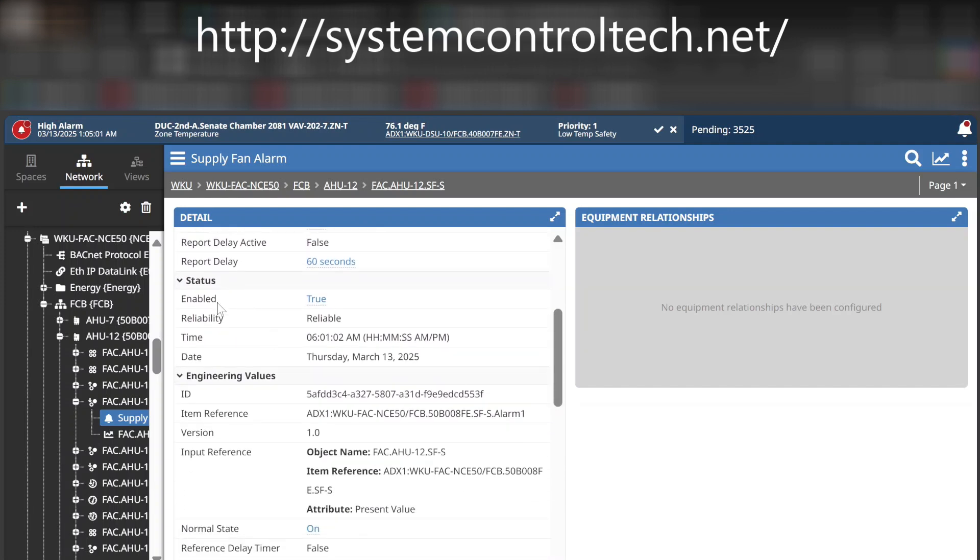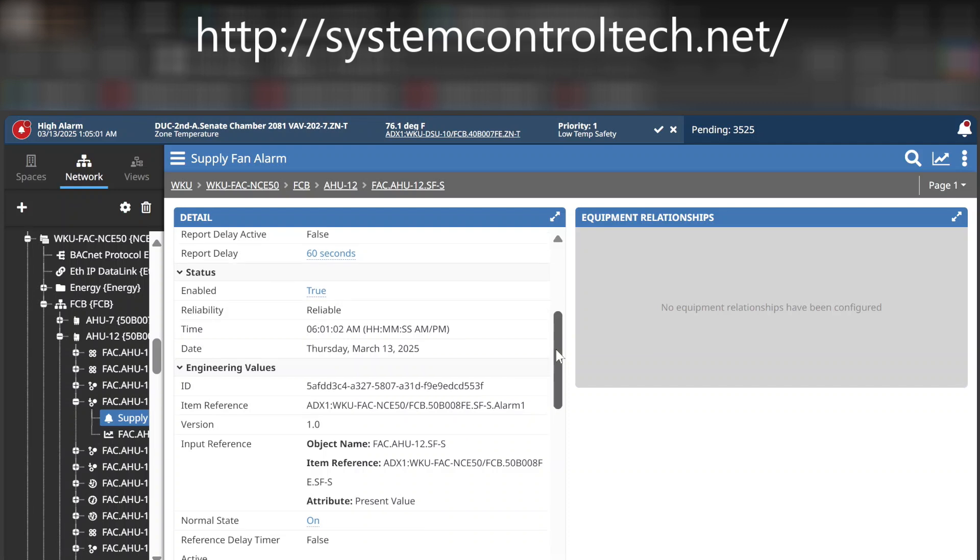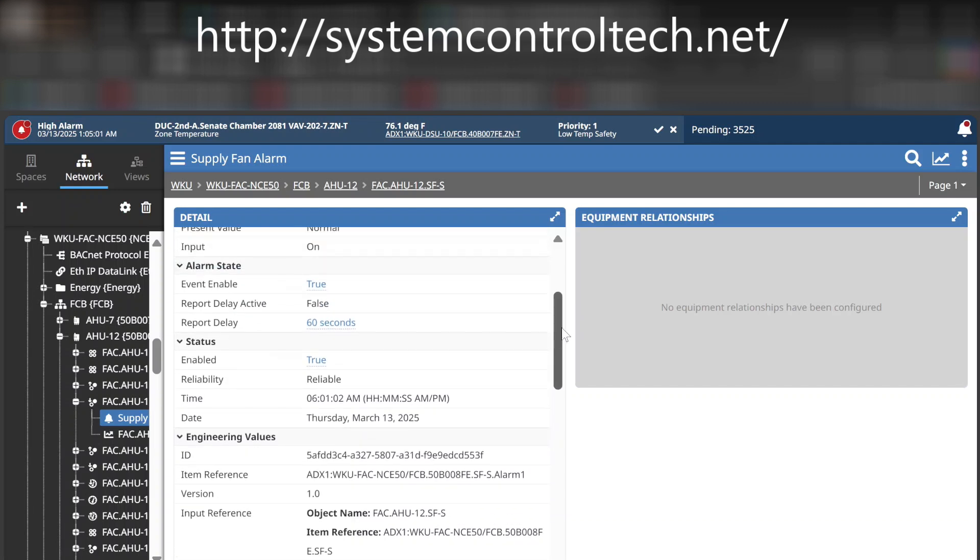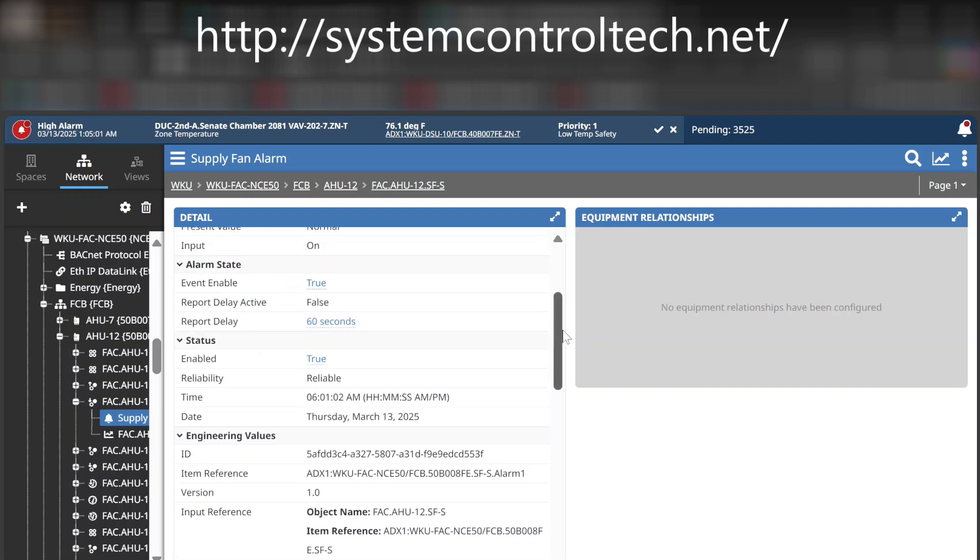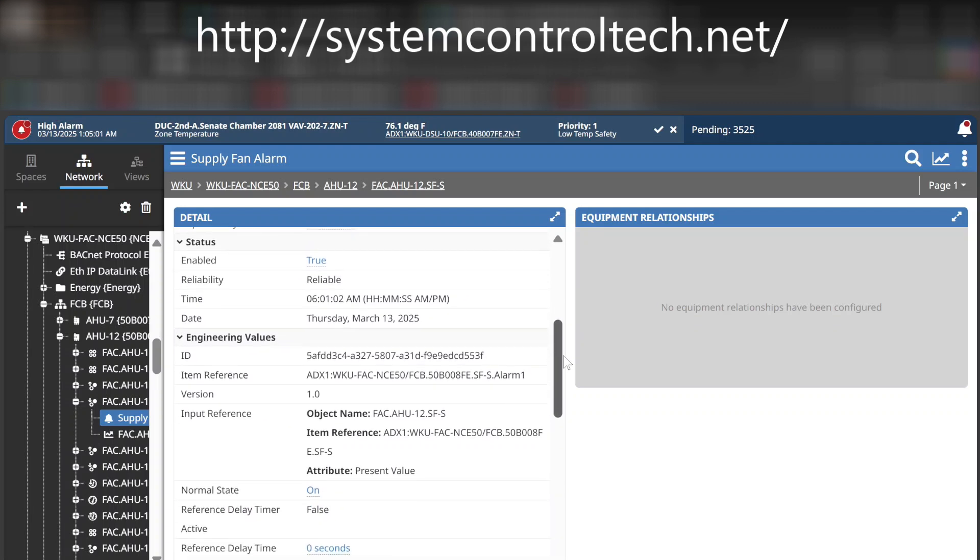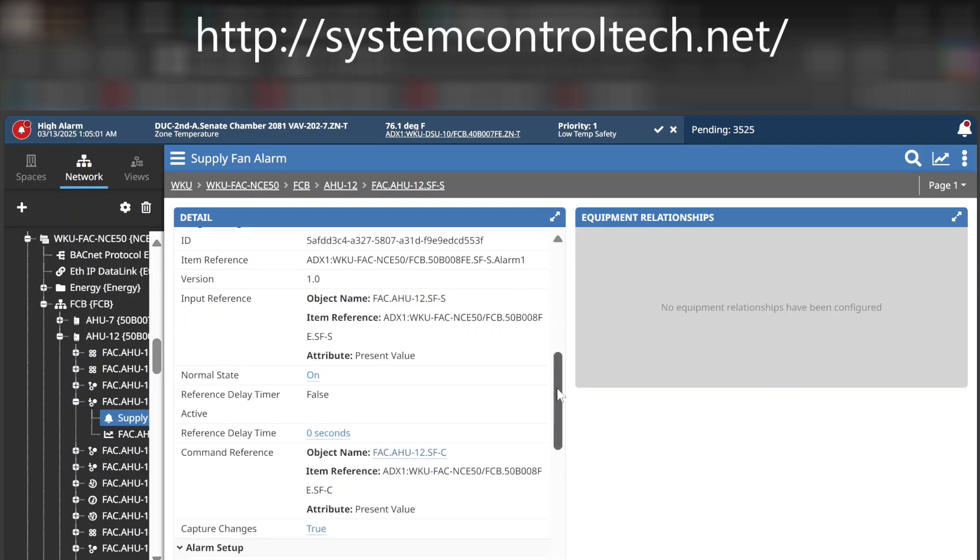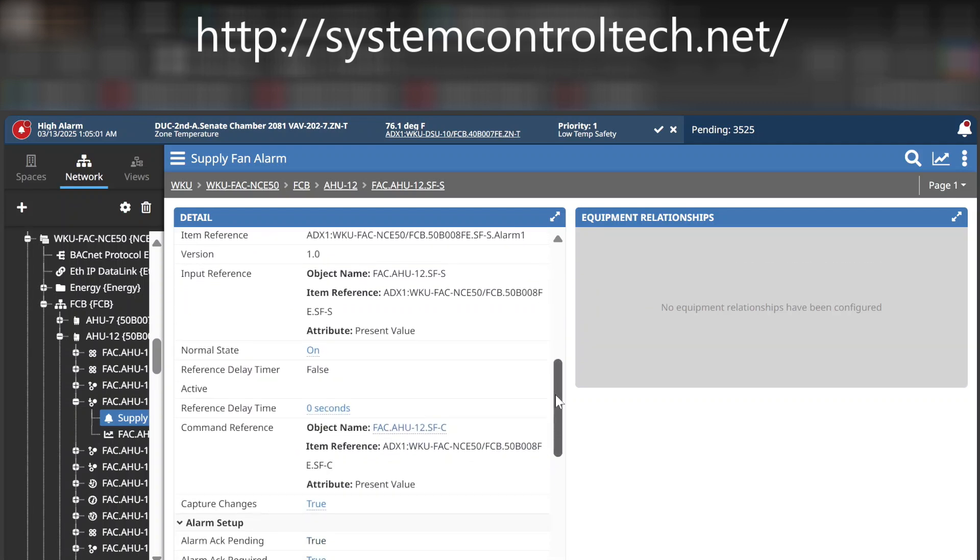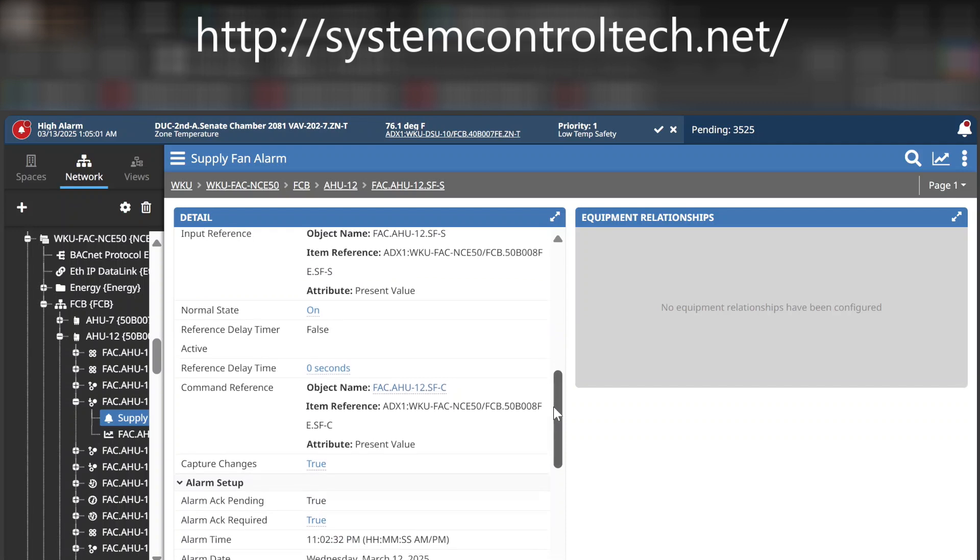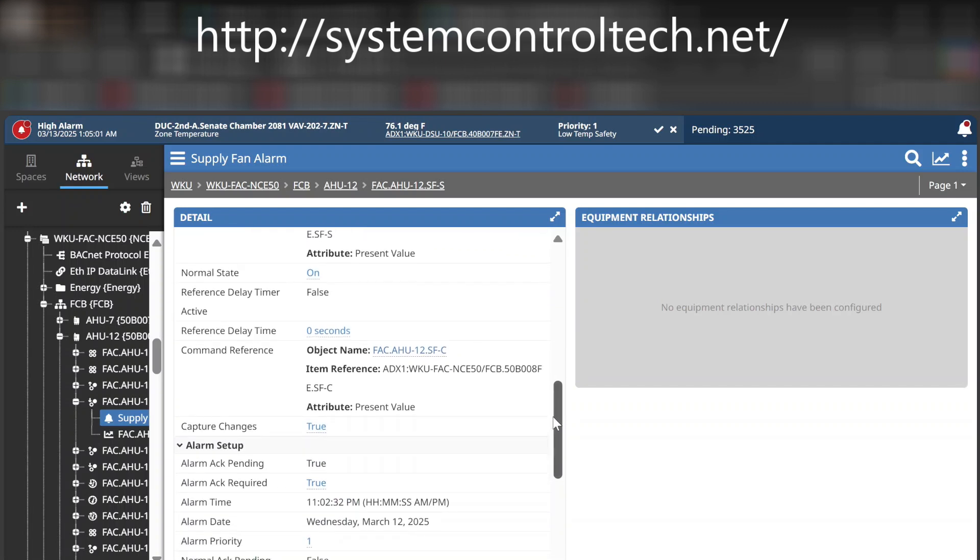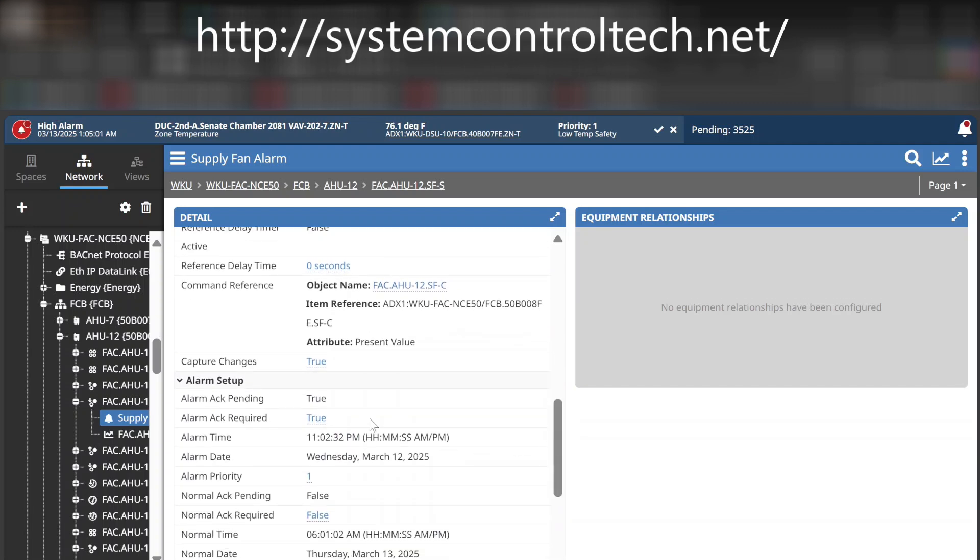Of course, I do have a report delay. I want to give it a little time in the morning for when that fan is first commanded on. I don't want it to instantly flag an alarm, so there is a delay there. I do have a command reference set up as far as it's looking at the command, and it's going to follow that. I can set up here my alarm acknowledge pending, alarm acknowledge required. If I do not want to require someone physically acknowledging that alarm on the system, I could set that to false. But there again, if you're going to make this useful, you might want to leave that to true. And this is the key right here, your alarm priority.